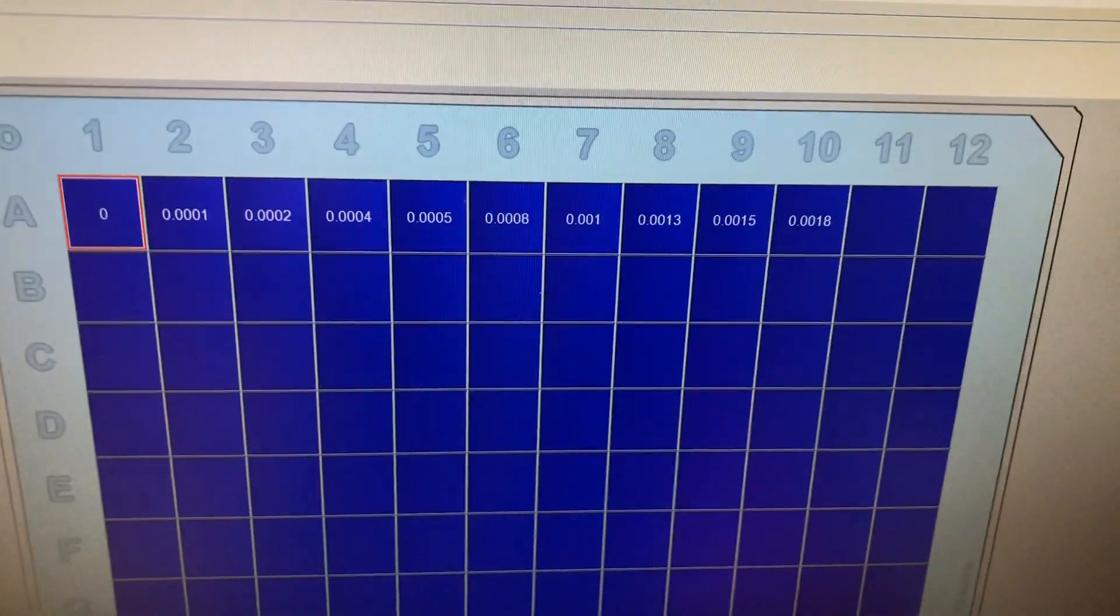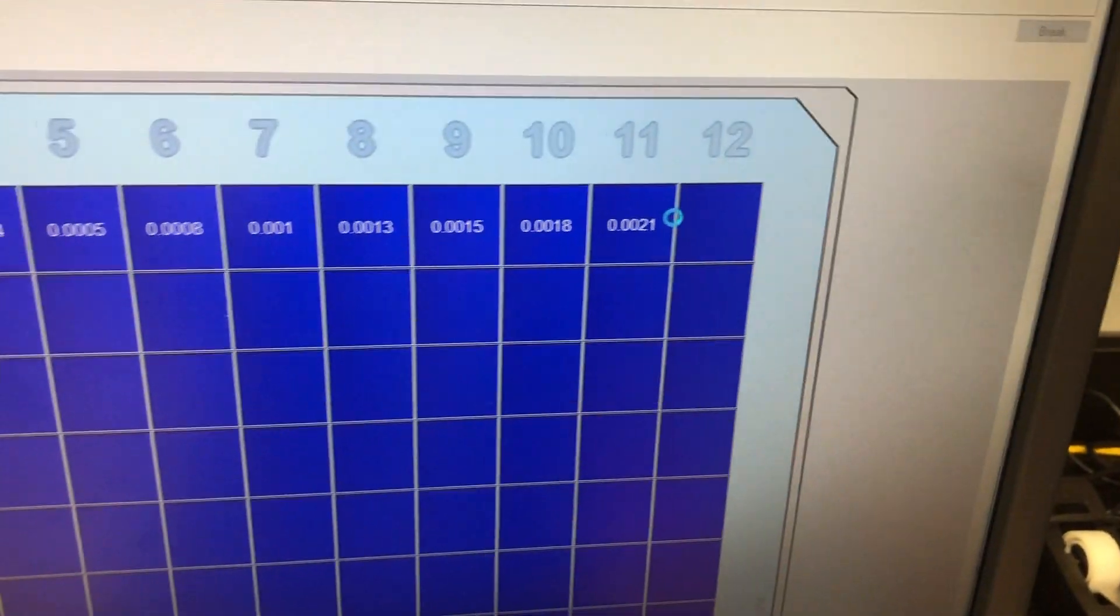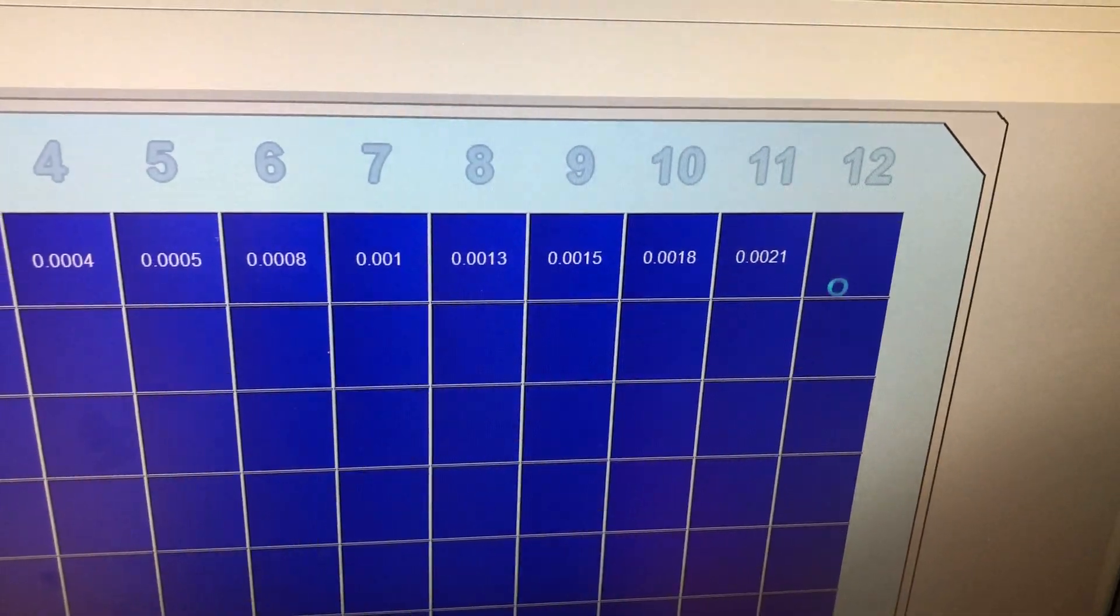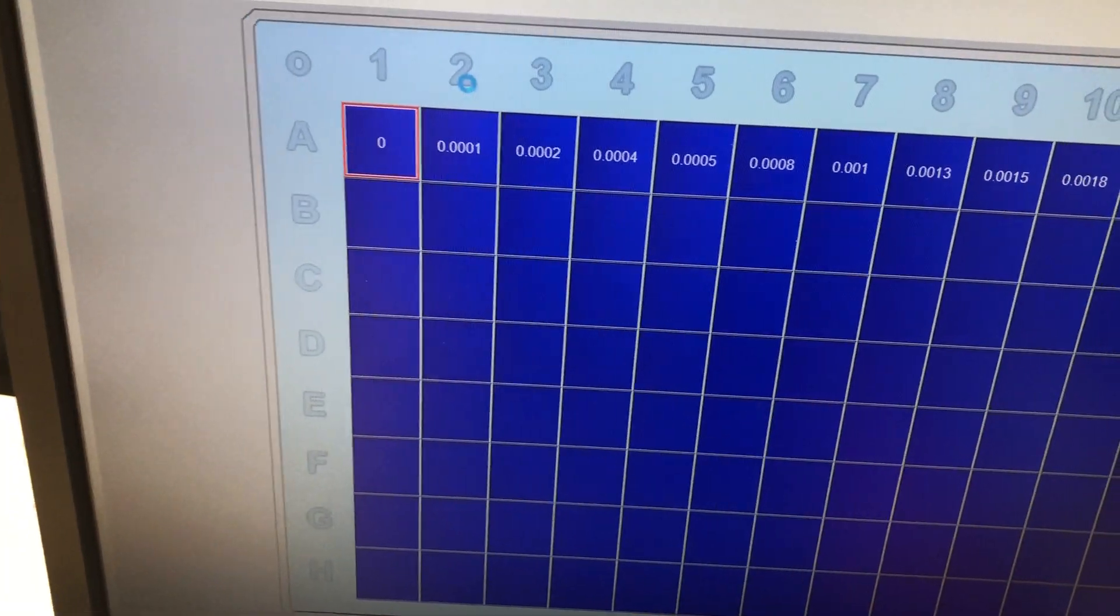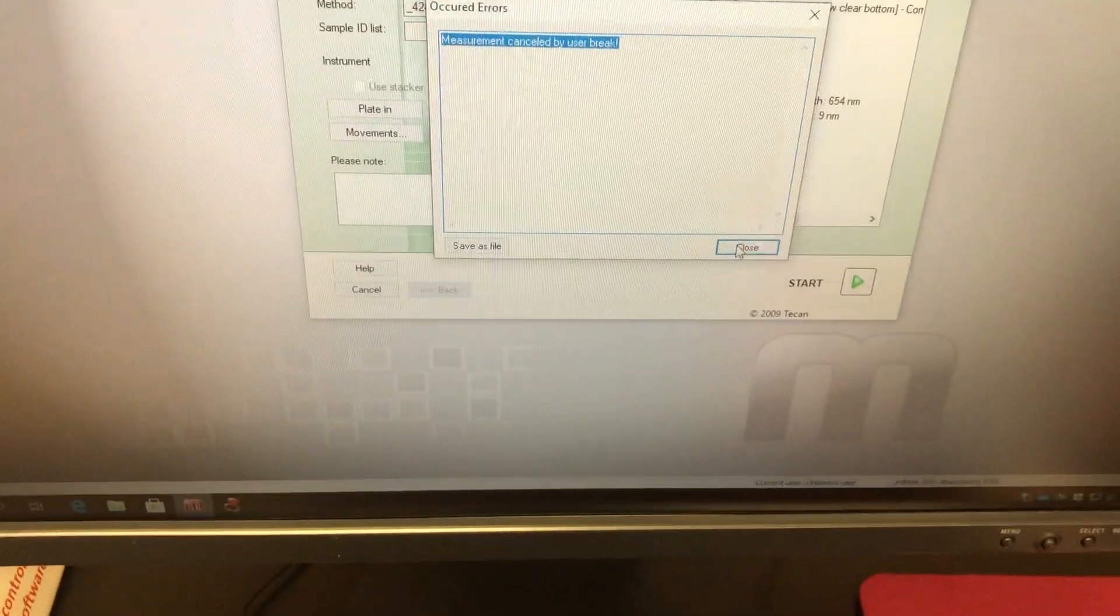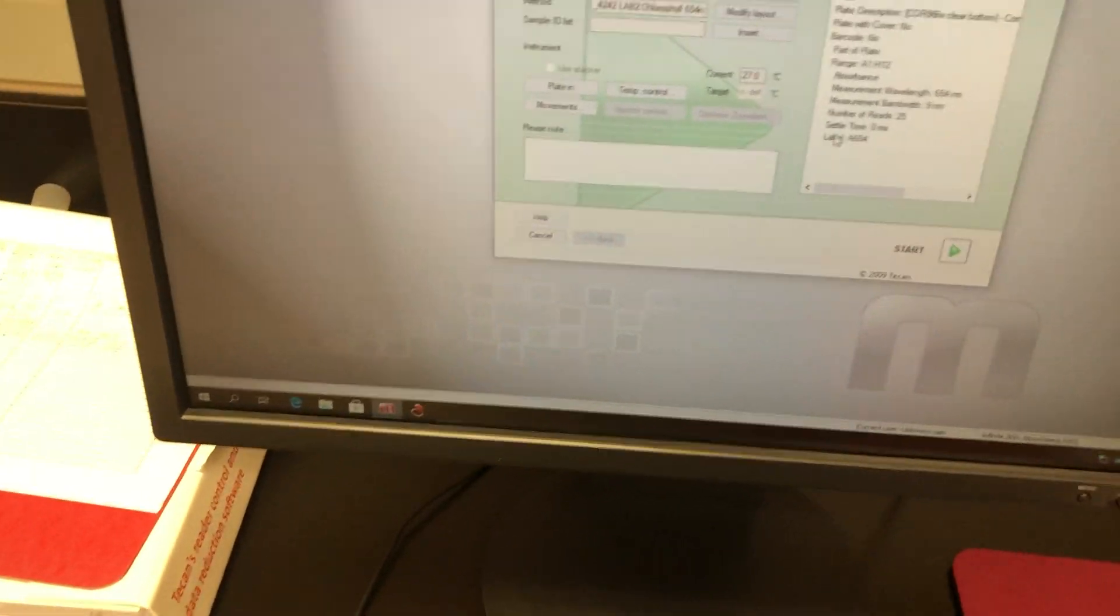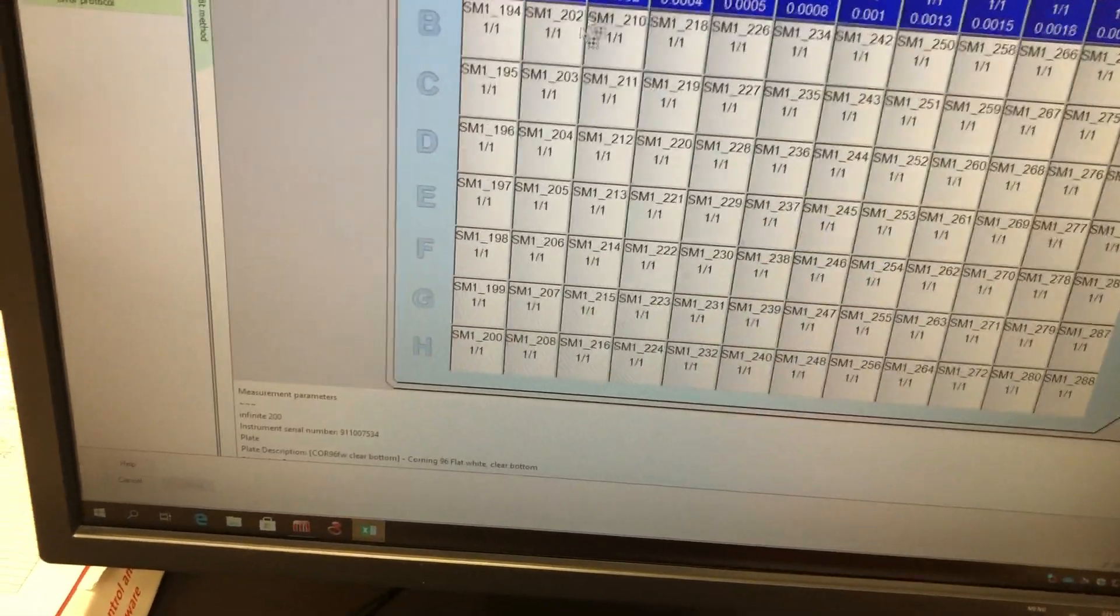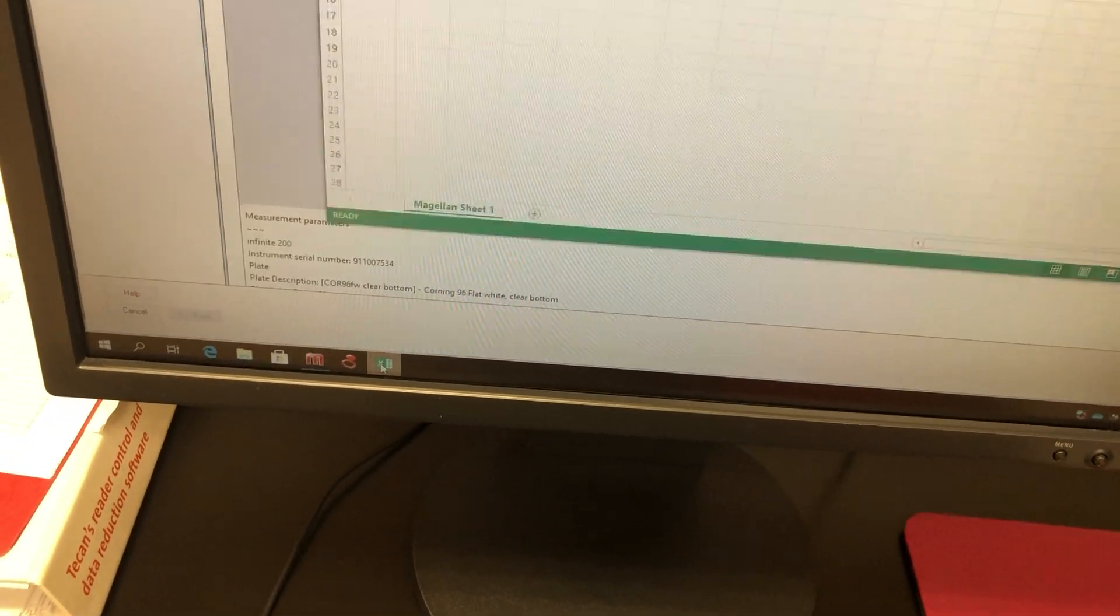And when it's done, I'm just going to break it so we don't have to read them all. There's a button up here. So you can see it kind of snakes back and forth. So it actually moves the plate and takes readings in each well, and then moves back this way. And I'll show you the data in real time as the data's coming out. And I just click abort. I'll finish up here. Yes, I canceled it. It should still spit out the data for me. It'll automatically export it into Excel. There we go. I see Excel is opening.